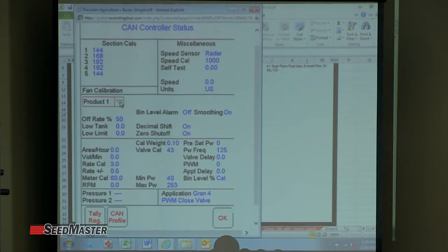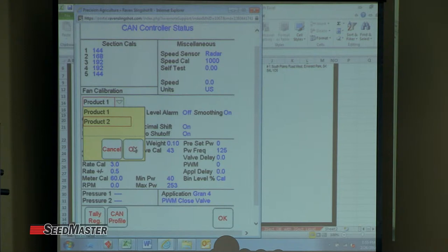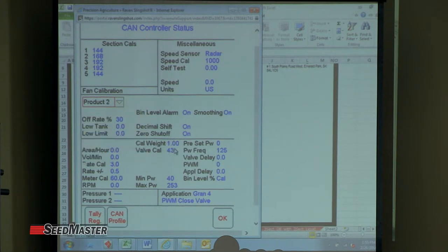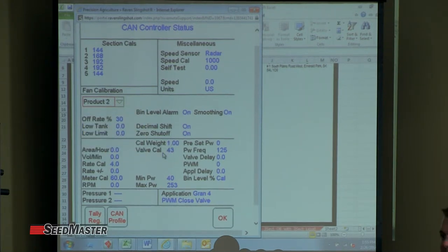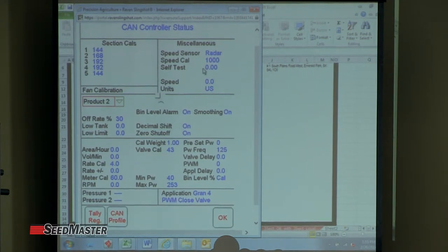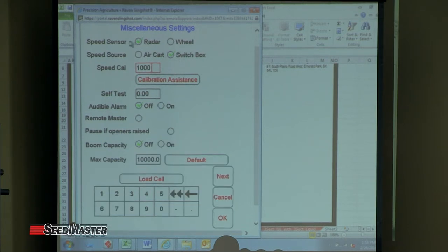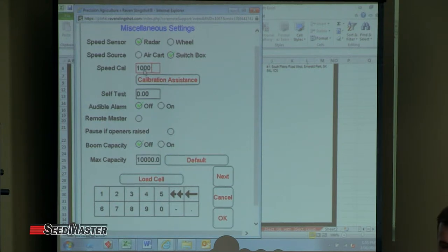So if I want to make a change to product two, I hit the drop down, change it to product two, then I would change my cal weight or whatever I'm making changes to. If I go into the miscellaneous, we've got speed sensor, radar, speed source, and switch box — that's where our speed cal comes in.